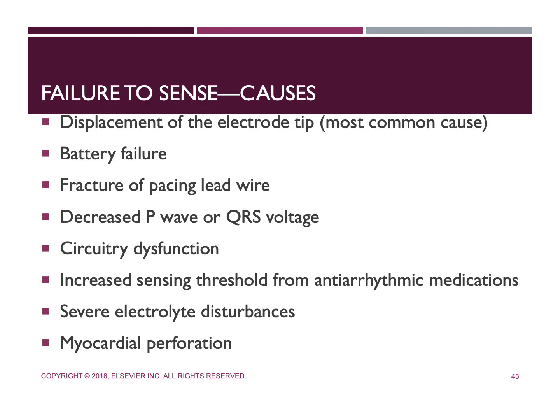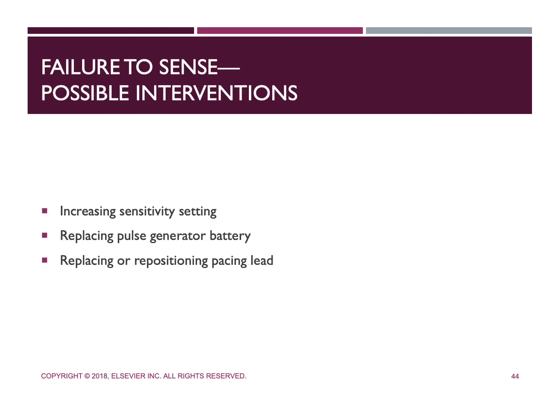These are some causes of failure to sense. Treatment for undersensing may include increasing the sensitivity setting, replacing the pulse generator battery, or replacing or repositioning the pacing lead. Treatment for oversensing may include adjustment of the pacemaker sensitivity setting or possible insertion of a bipolar lead if oversensing is caused by a unipolar lead dysfunction.